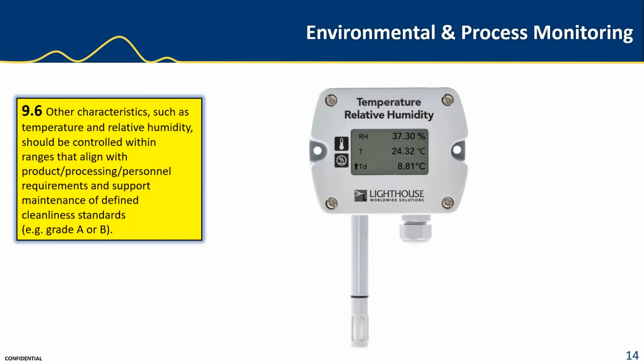So I've seen cases where a facility is using one sensor for control with their BMS and monitoring, and using that sensor data for batch release. And the FDA really comes in and says that's a nope. They do not want to see one sensor for control and also using that data for validation. You need to have separate sensors. And I've seen facilities where the customer has had to add in the extra sensors whenever the FDA or any other regulatory body, and actually over in Australia, we had the regulatory body over there and a couple of companies nearly shut down production because of that. And we went in and retrofitted a couple of environmental monitoring systems with the correct sensors and types independent of the BMS.